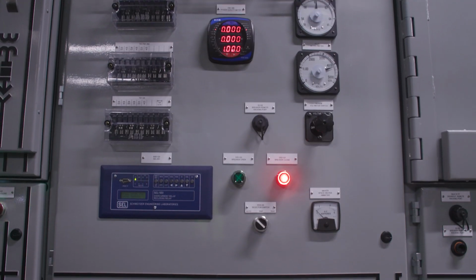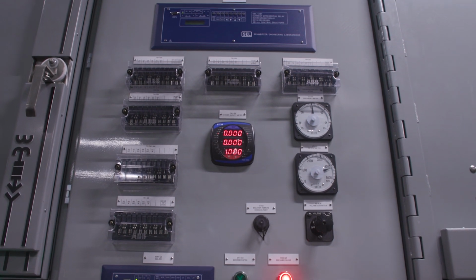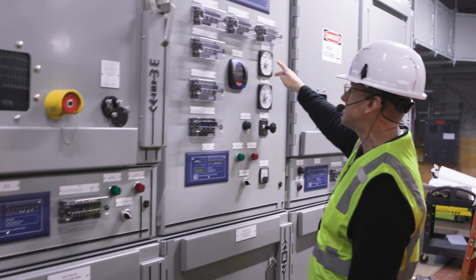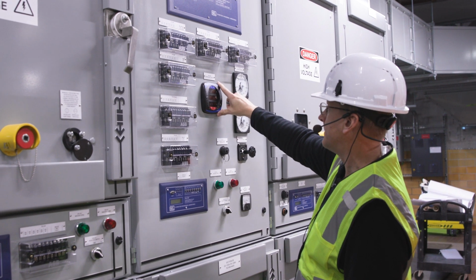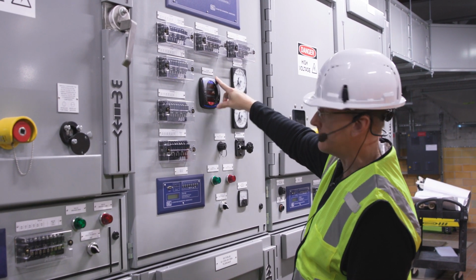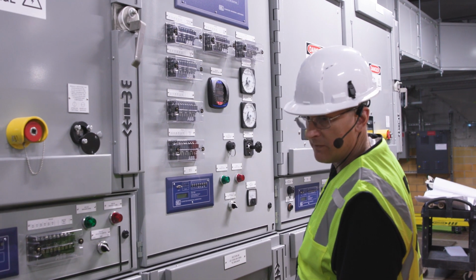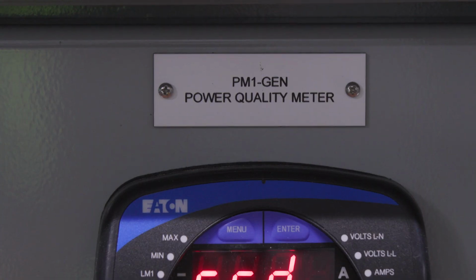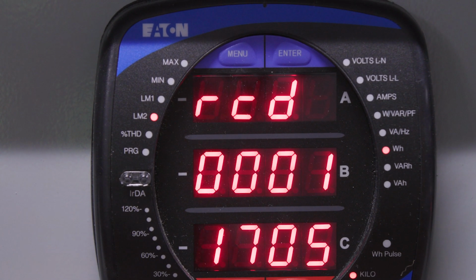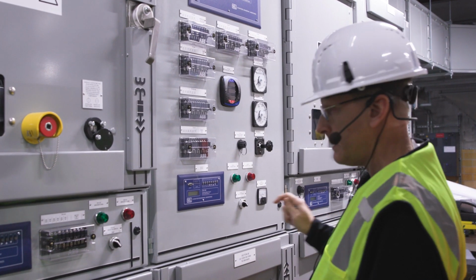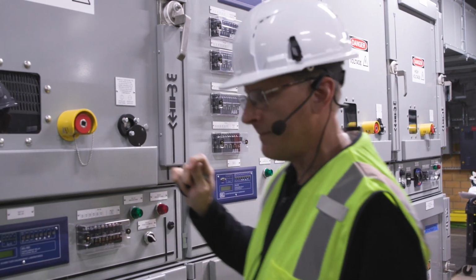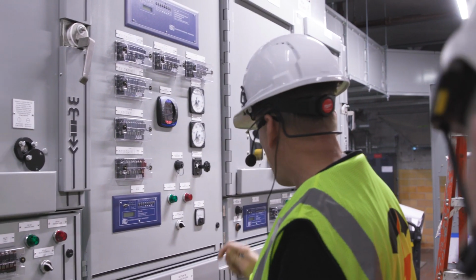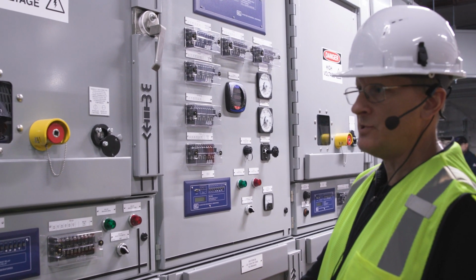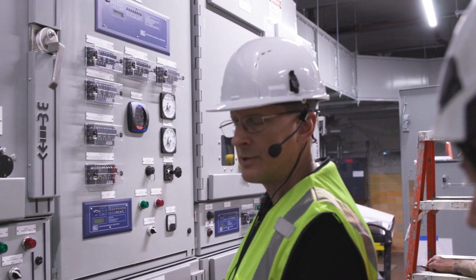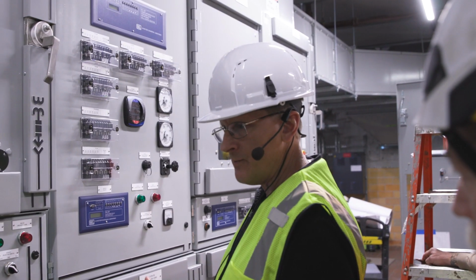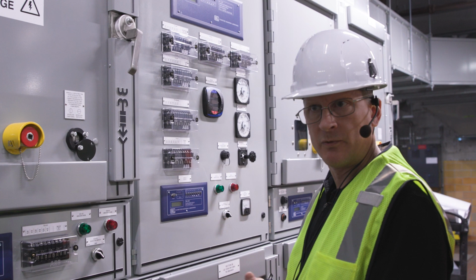Various meters as well on the gear itself. We've got mains voltage and frequency on these 2 meters. We've got the actual meter for the output bus right here, and then on the extreme end we've got a meter just for the generator output itself. All of these breakers and the PTs, you'll notice, have a racking interface that you can manually rack out the breakers in PT drawers. However, the system also came with an automatic racking system for racking in and out the breakers.